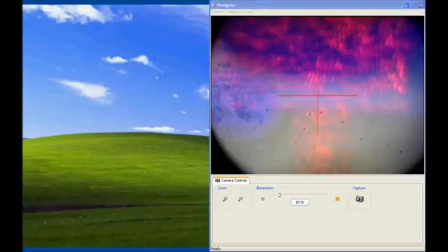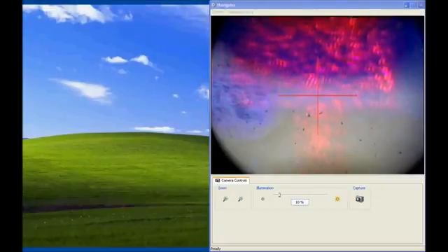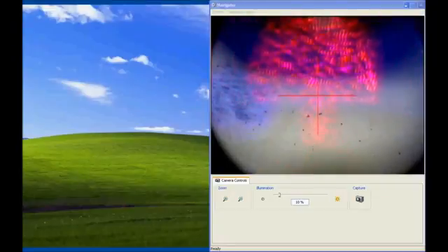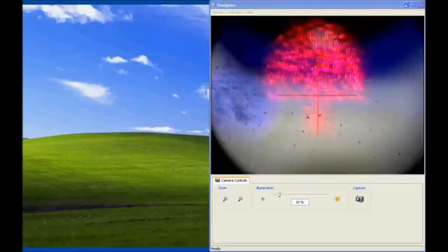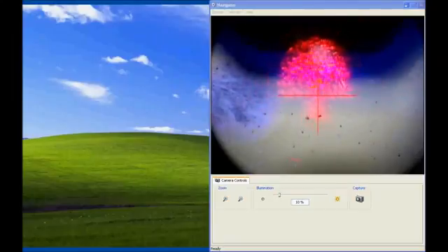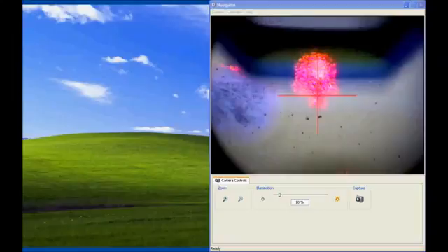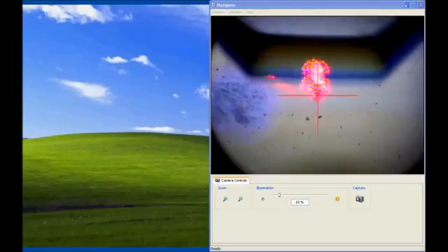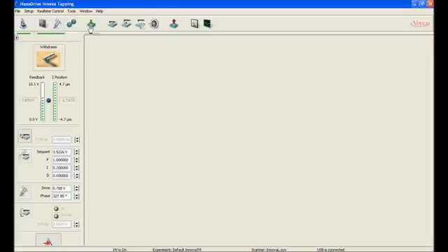We can also watch the microscope. As the tip approaches the surface, it comes into focus. Remember, we don't want to actually touch the surface, just get close, so don't bring the tip completely into focus or it will touch the surface. Click the Engage button, the fifth icon shown here, to bring the tip into contact.